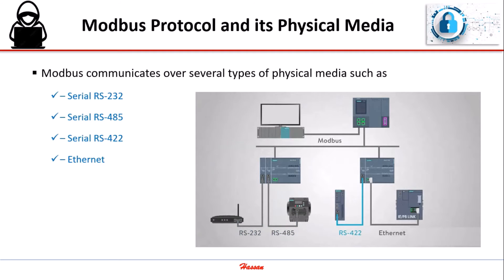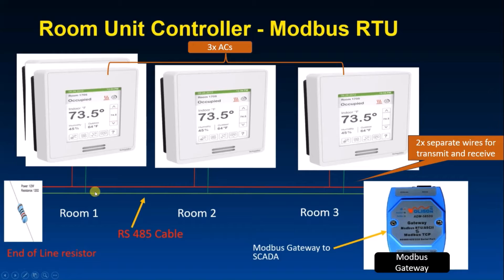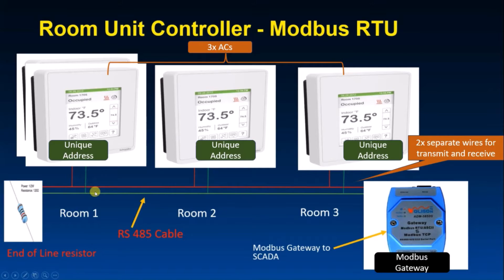Modbus communicates over several types of physical media, with serial RS-485 being the most popular method used. For example, in a hotel with several air conditioners, from a main computer we can control each air conditioner by giving a unique address to each one. We can see two communication lines A and B connected in parallel with each AC — one wire transmits data while the other receives data. A Modbus Gateway is used for data conversion between different types of Modbus devices and media, and this is a typical setup in any industry.